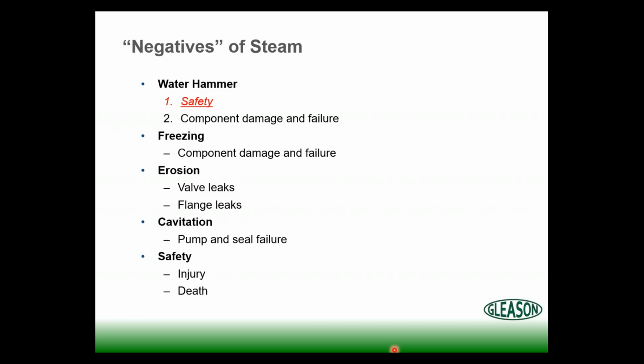Erosion can be an issue. Steam carrying water along with it is very, very erosive and will cut metal. It will wire draw valve seats, that kind of thing. Cavitation, we'll talk more about that when it comes to your centrifugal condensate pumps. And it all comes back to net positive suction head required.